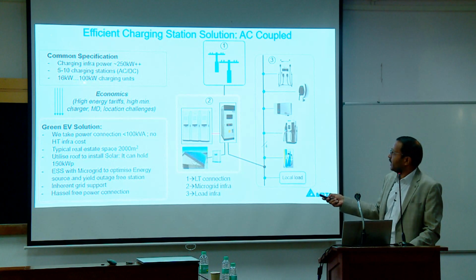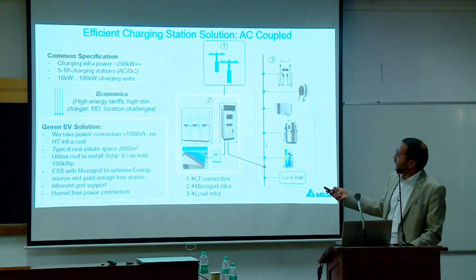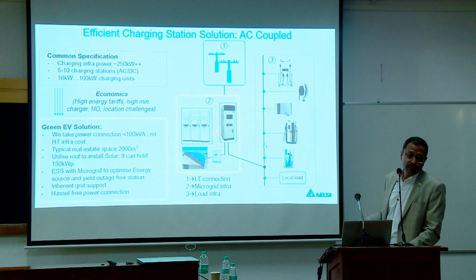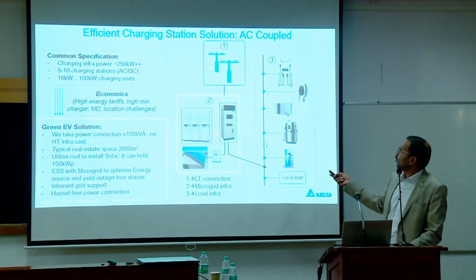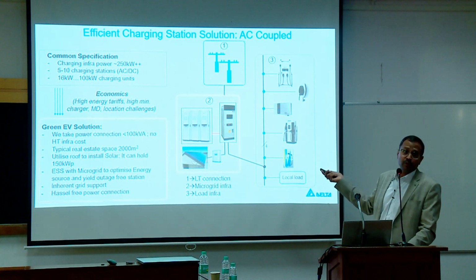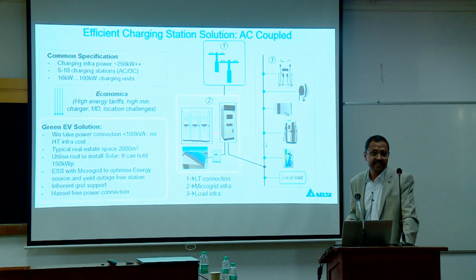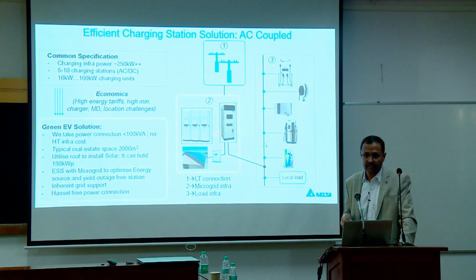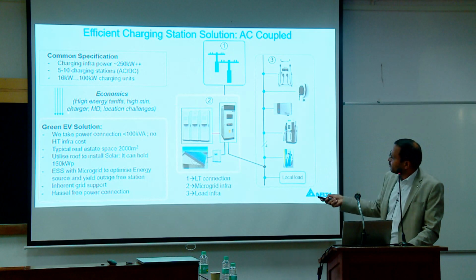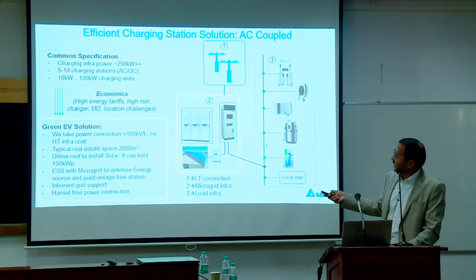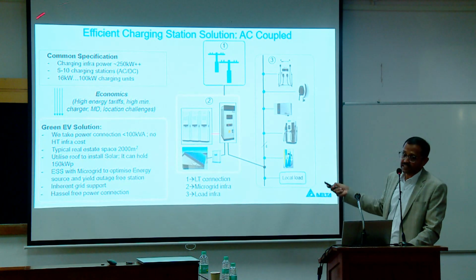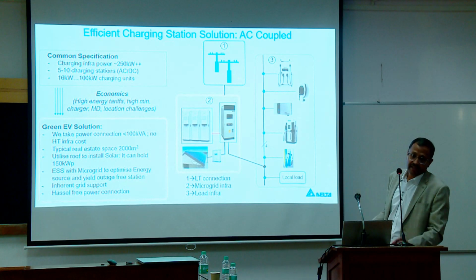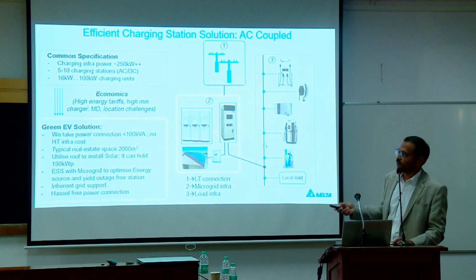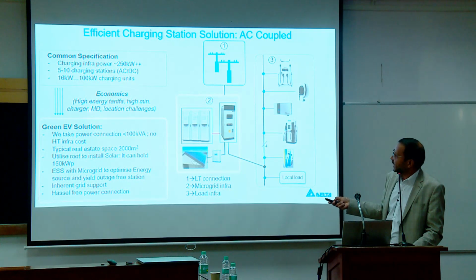Let's say if you have 100 kilowatt kind of chargers, you would need a connection from the electricity board of about 250 kVA. The moment you go more than 100 kVA, you need your own transformer. You have to have an HT connection - either 11 kV or 33 kV. This will demand high energy tariffs and high minimum charges because your connected load is very high, and that also adds to your maximum demand charges.